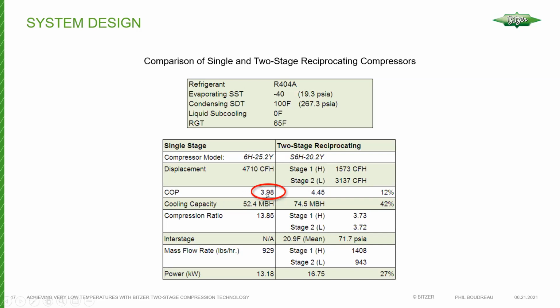The coefficient of performance for the single stage is 3.98. The coefficient of performance for the two stage goes up a bit to 4.45, which is a 12% increase, which is nice. It's always nice to see higher efficiency numbers. It doesn't tell the whole story, but that's part of it. Capacity is 52.4 thousand BTUs per hour for the single stage, and then the two stage is 74.5 thousand BTUs per hour. In this case, your increase in capacity is 42%. So 12% higher efficiency, but you're getting a lot more capacity. So that's another part of the story there.